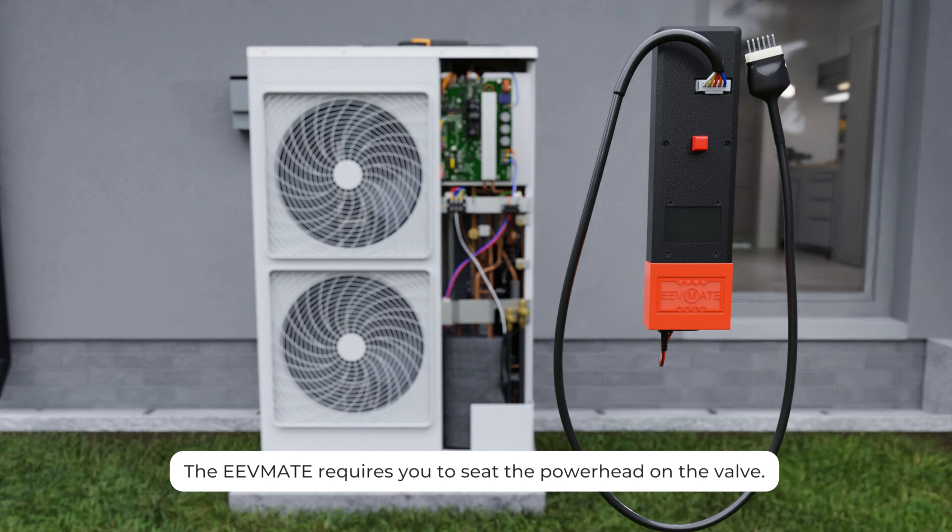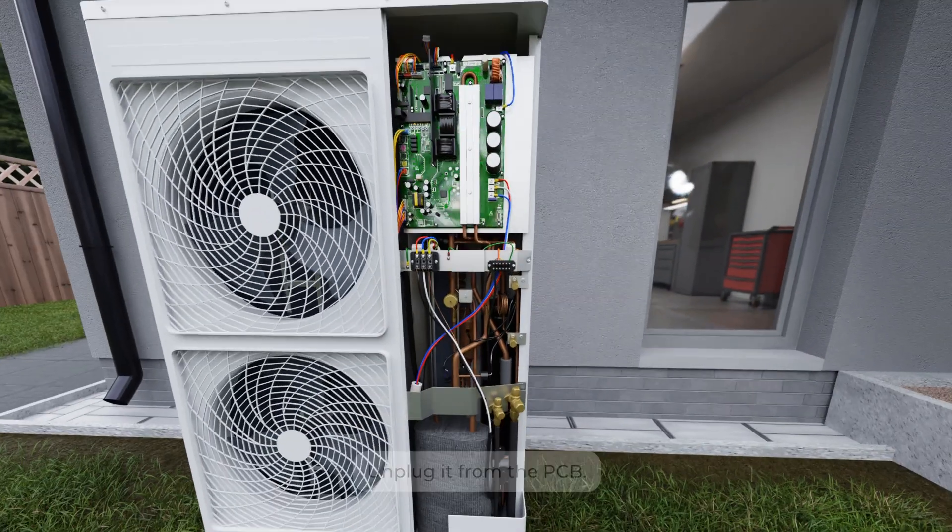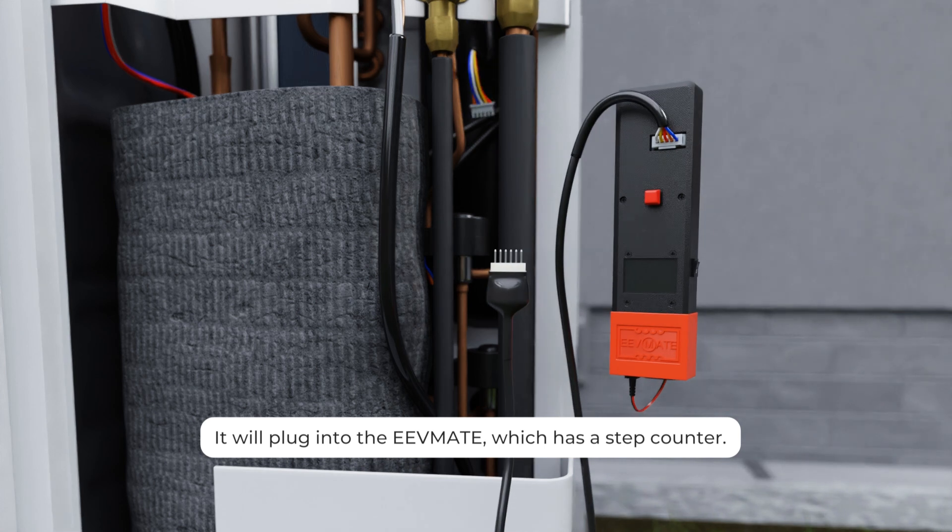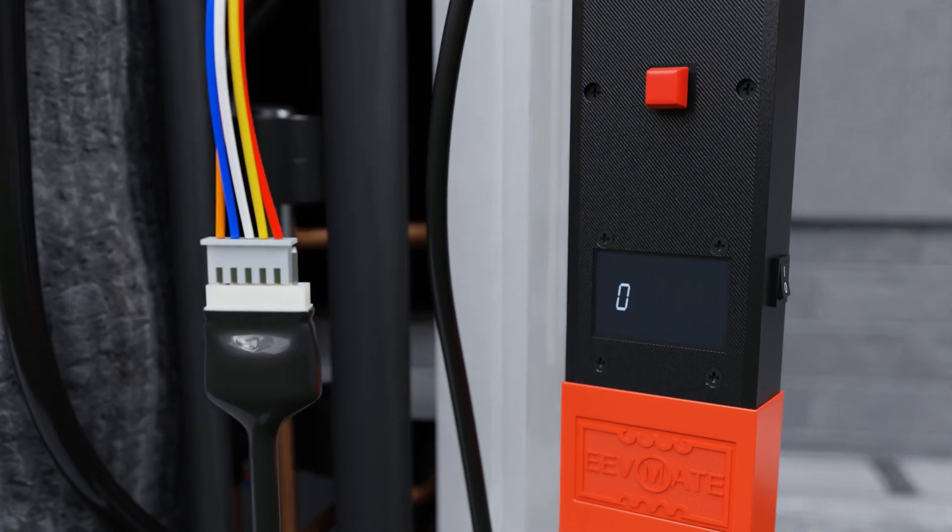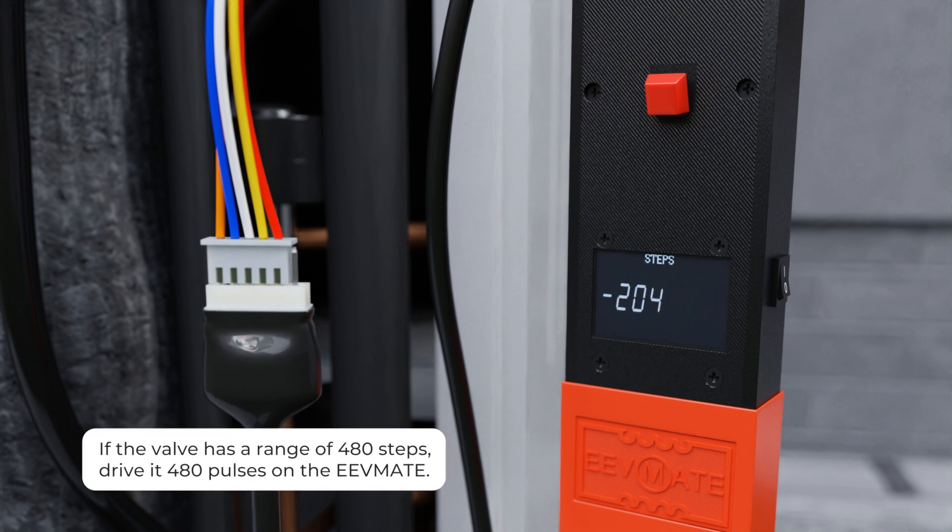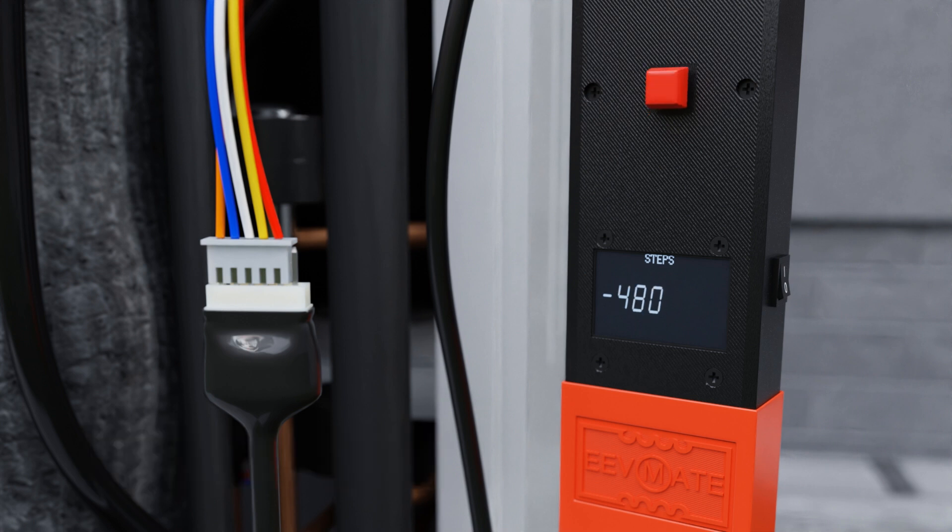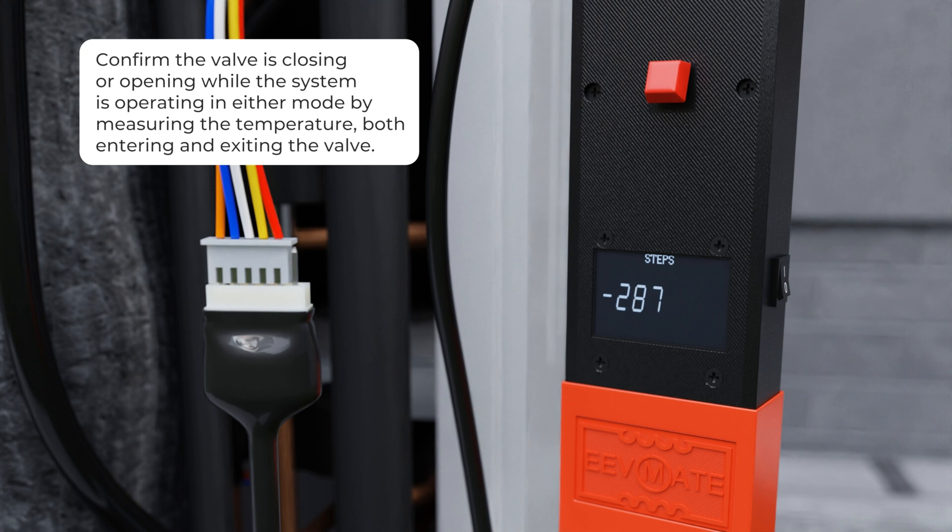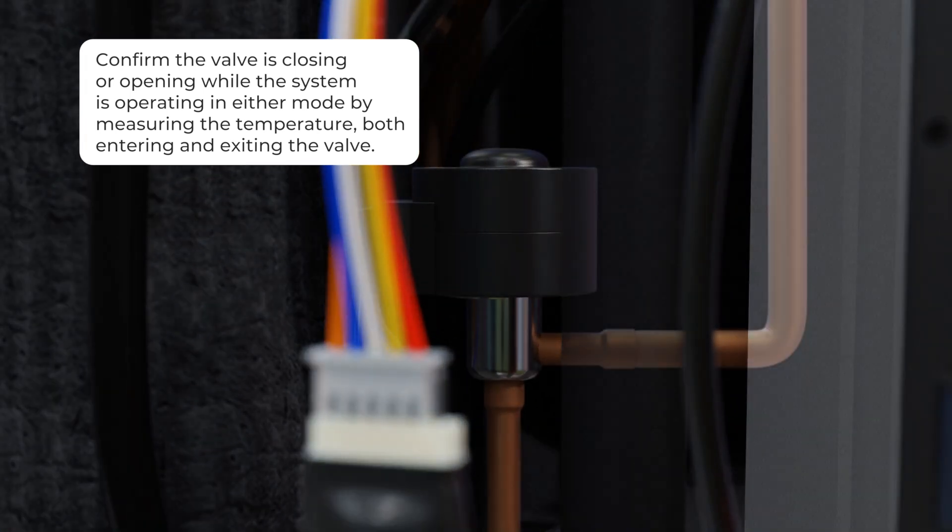The EEV Mate requires you to seat the power head on the valve but unplug it from the PCB. It will plug into the EEV Mate which has a step counter. You will then drive the valve manually using the EEV Mate tool. If your valve has a maximum range of 480 steps, we want to drive the valve 480 pulses on the EEV Mate. Confirmation of the valve closing or opening can be confirmed while the system is operating in either mode by measuring the temperature, both entering and exiting the valve.